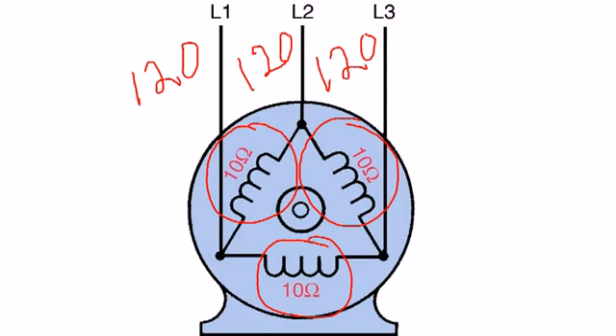The nice thing about a three-phase motor is if you swap any two leads going to that motor, you'll reverse the direction of rotation. So in a case like this, if you just swap L1 and L2, it'll start turning backwards.